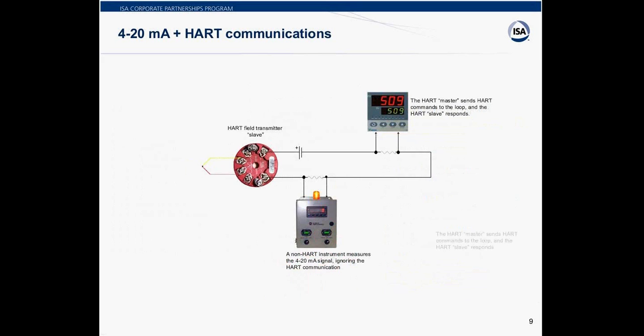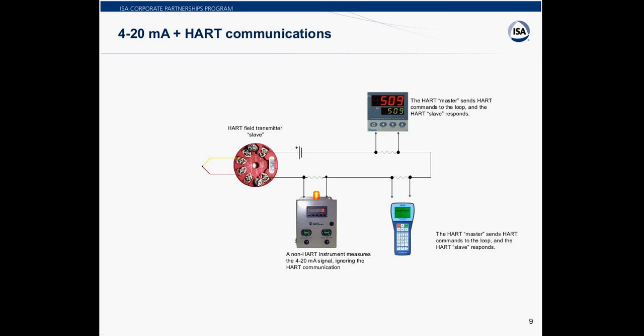You can also connect a second HART master to the loop — this master could be a calibrator or a portable, battery-powered HART communicator. Since this master is portable, you can communicate with the HART transmitter from anywhere you can physically access the loop. In most cases, a permanently installed HART master is not used. Most HART loops only use a HART handheld communicator, which is temporarily connected to the loop and used to configure or troubleshoot the HART transmitter. Once the communicator is removed, the HART transmitter receives no commands and in most cases will just behave like a standard transmitter.